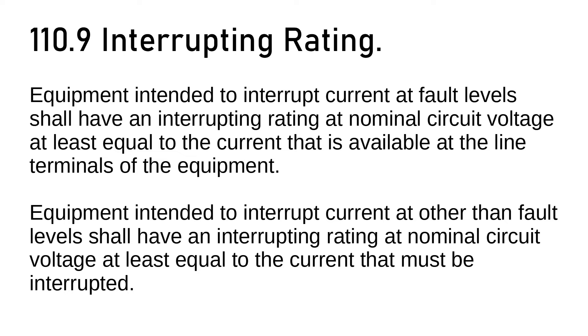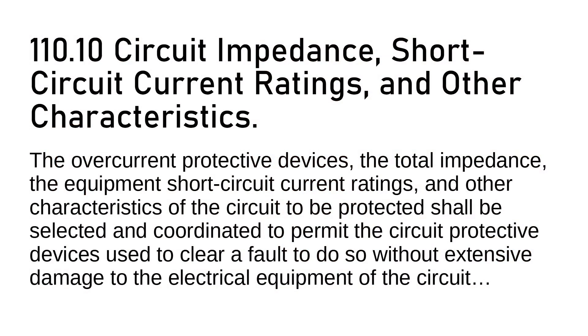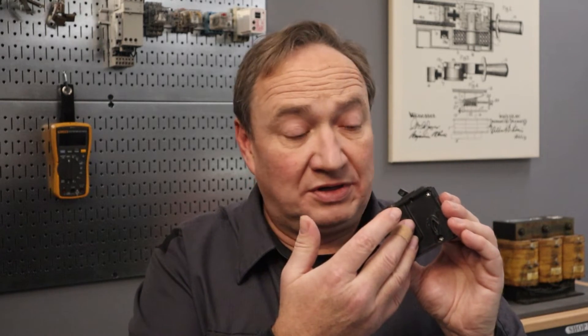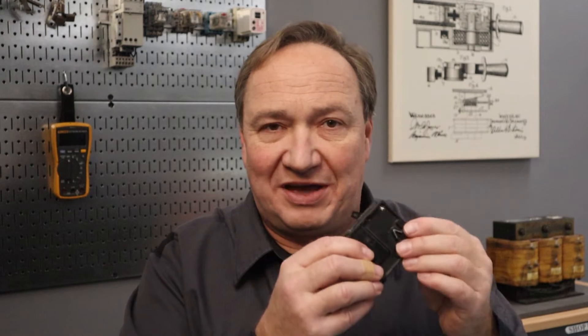NEC 110.9, Interrupting Rating: equipment intended to interrupt current at fault levels shall have an interrupting rating at nominal circuit voltage at least equal to the current that is available at the line terminals of the equipment. And then 110.10 also requires that equipment short circuit current ratings and other characteristics of the circuit to be protected shall be selected and coordinated to permit the circuit protective devices used to clear a fault to do so without extensive damage to the electrical equipment of the circuit. So if I've got a breaker or a fuse that protects my electrical circuit, when it trips under a short circuit, we want it to stay together — we don't want it to blow apart. We have to be within that rating.